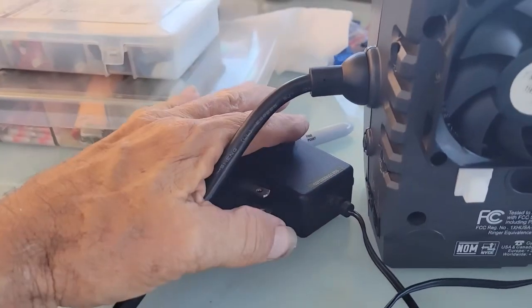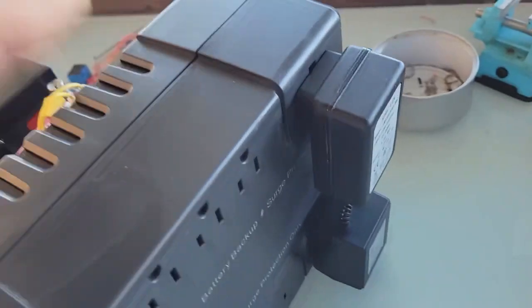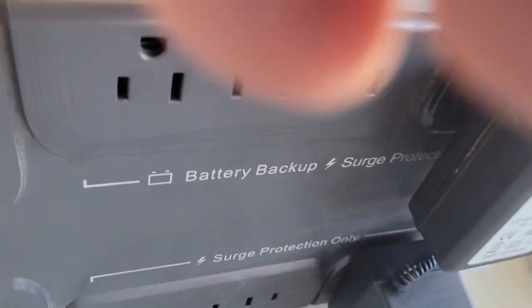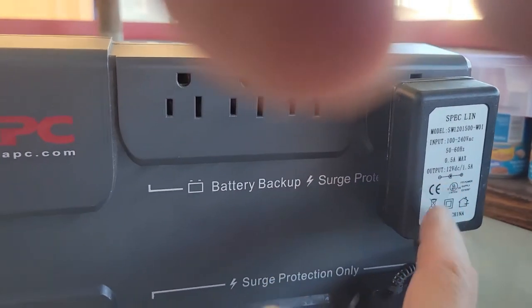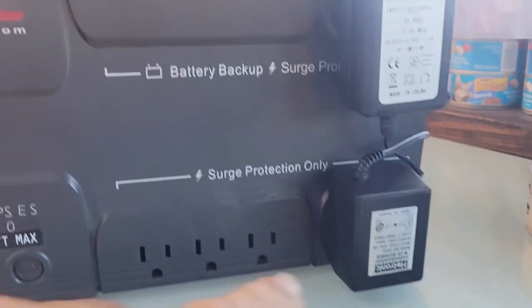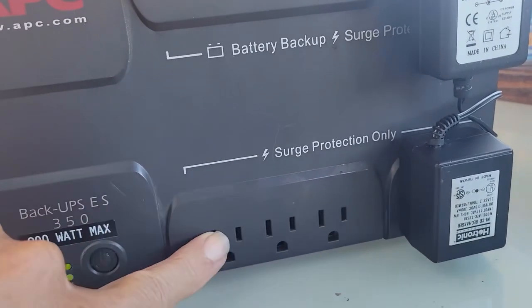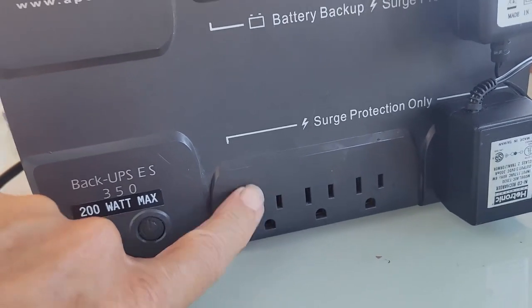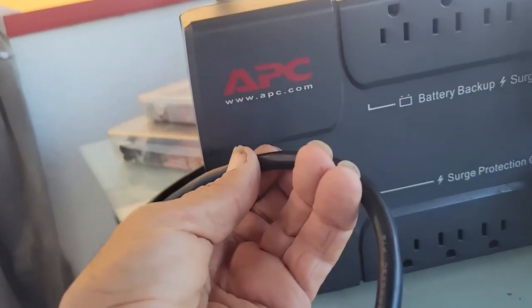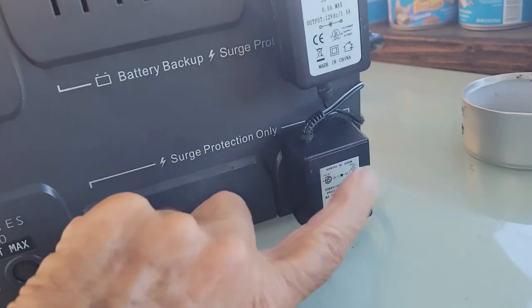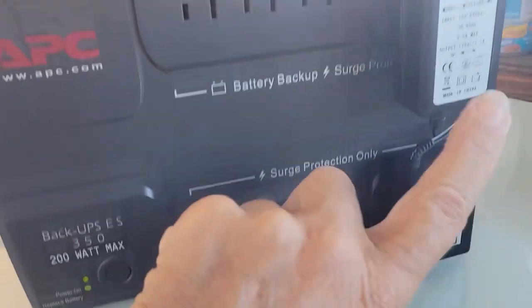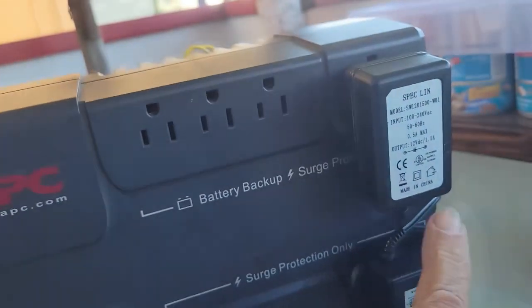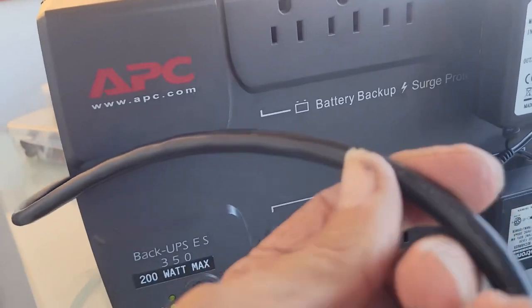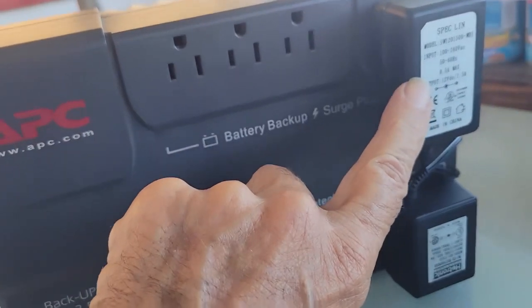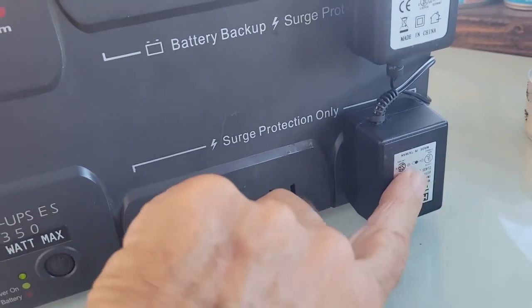Now let's plug in the transformers and I'll show you what's going on. There are 2 transformers: one controlling the relay, which is a 3-volt relay with a 3-volt transformer, and a 12-volt transformer going to the fan. The 3-volt transformer is plugged into the surge only, so when we lose power to the UPS, we lose power to this, and it throws the relay. This one is on continuous power, so it'll have power when we have AC, and it'll have power when we go to battery. But this one is going to control the relay.